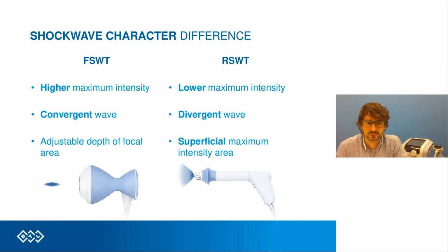When it comes to adjusting the depth, I mentioned the coupling pads, but let's say the clinical use for this is that with the focused shockwave, you can adjust the depth of the maximum intensity however you want. And at the same time, you can set how intense it will be. With the radial shockwave, you can only set how intense the shockwave will be, but not how deep it will get inside the tissue.